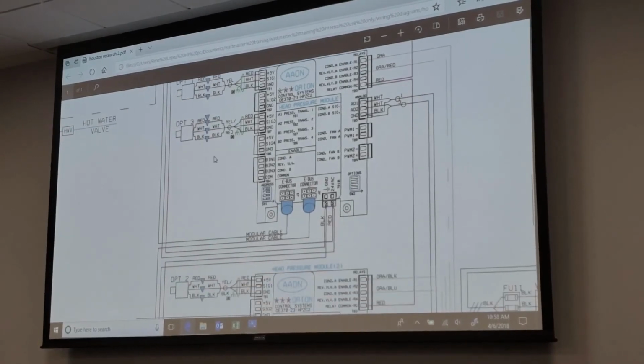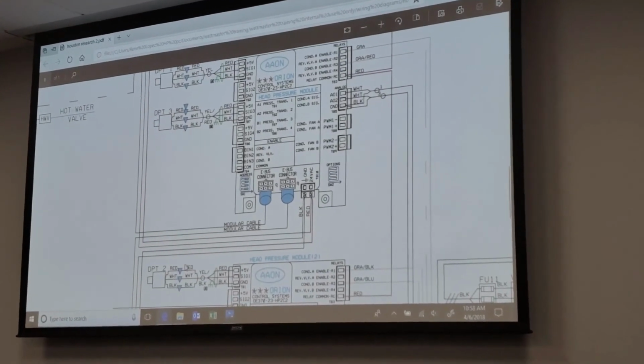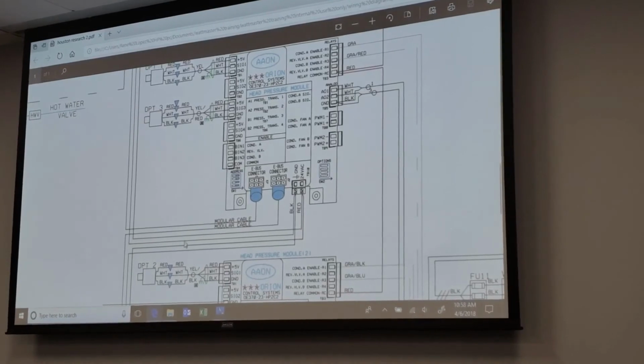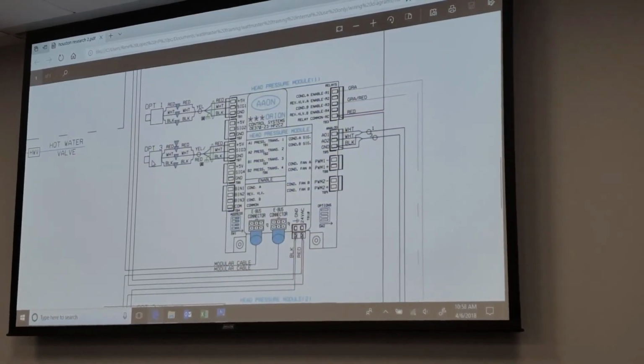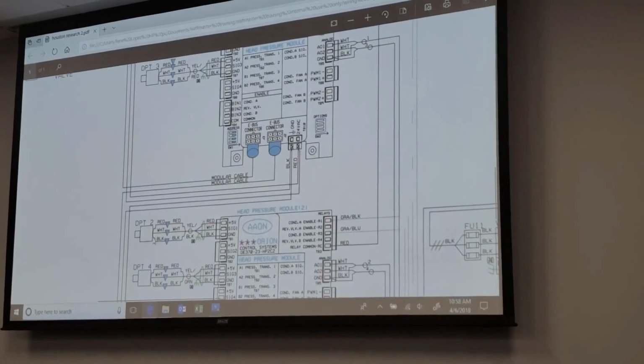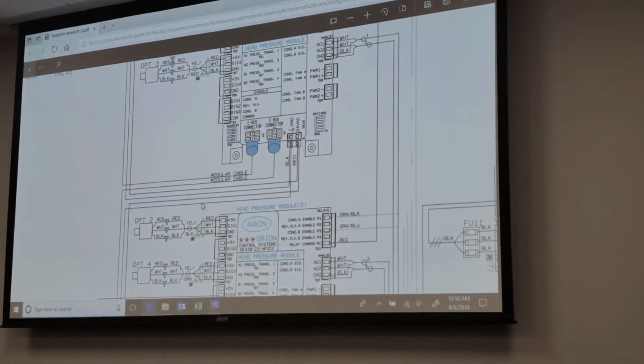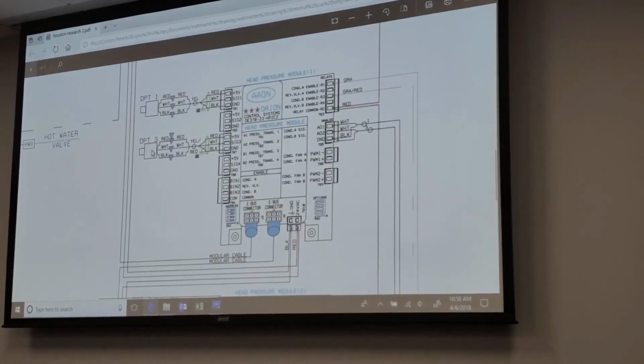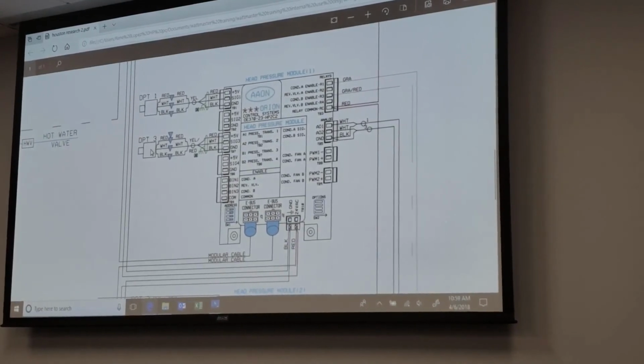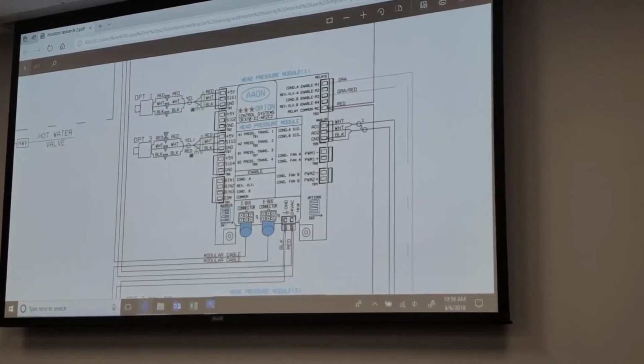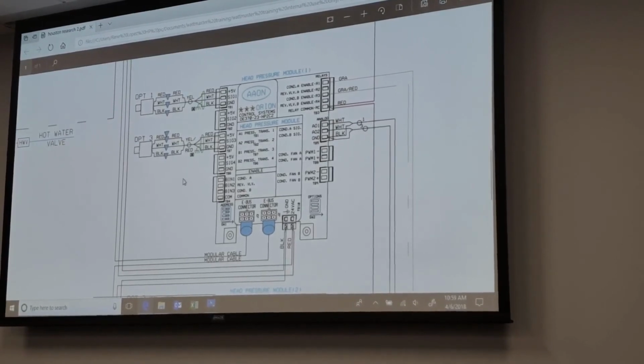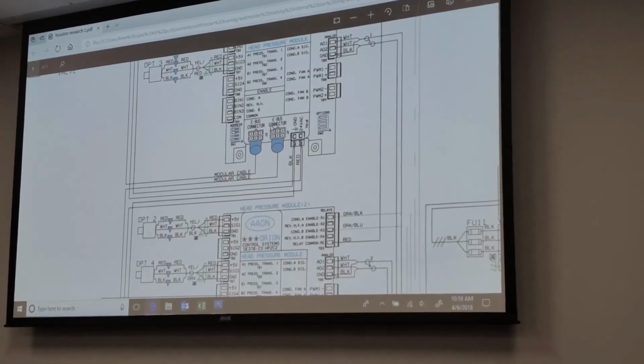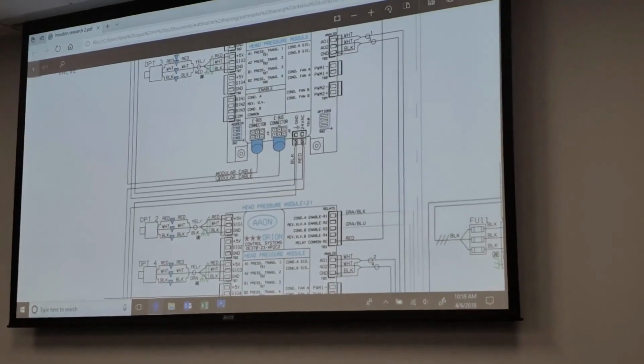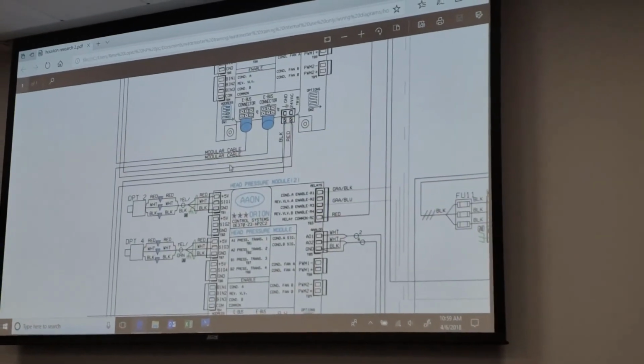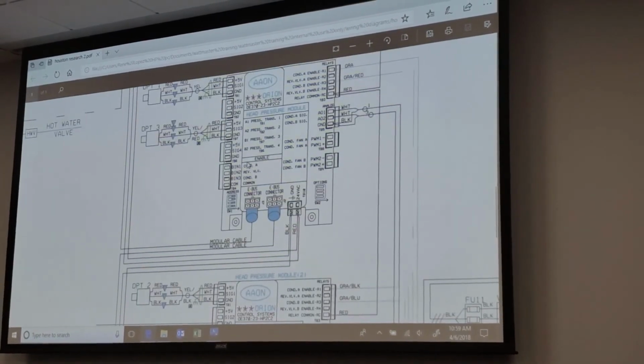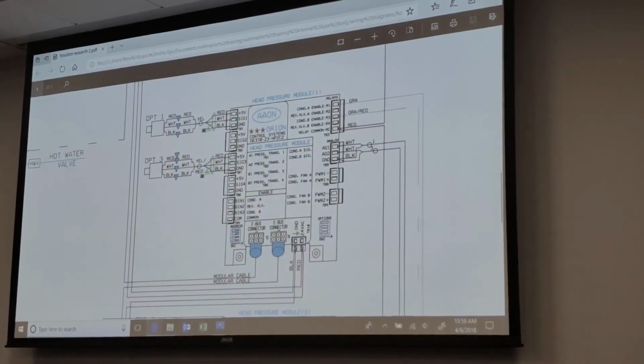One of my guys went out there, and it was always a problem with compressors 2 and 3 tripping on head pressure. Well, when number 2 would come on, the pressure was over here on the wrong output. It would fire this guy. This compressor wasn't running, so it didn't care. Eventually it would trip off on discharge pressure because it didn't get the output. So those are things to look at. We actually had to call the factory and say, hey guys, we need a new print. On all these jobs that we're looking at right here, we called the factory and said, your print's wrong.